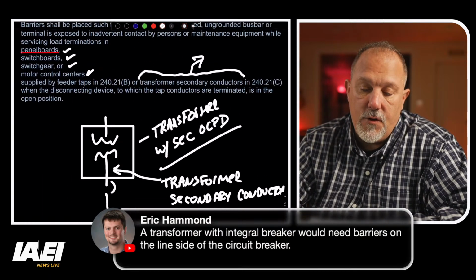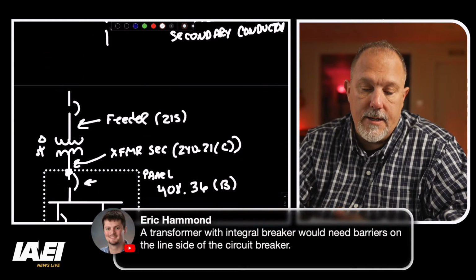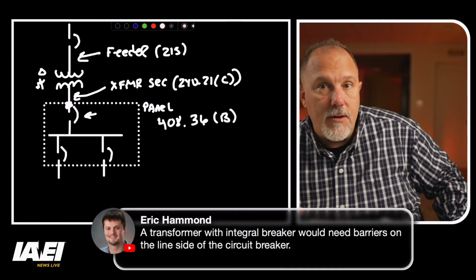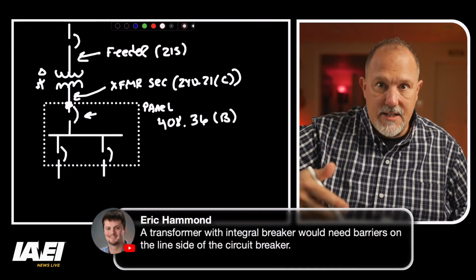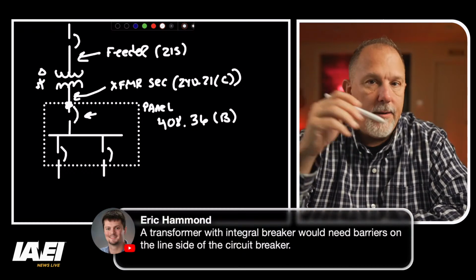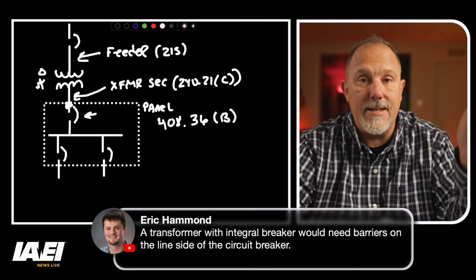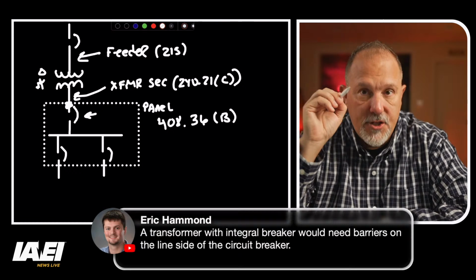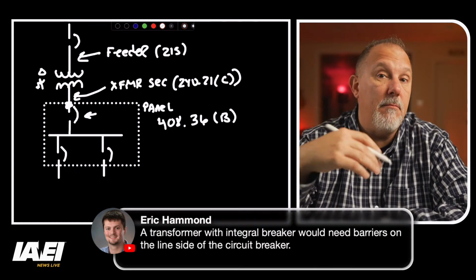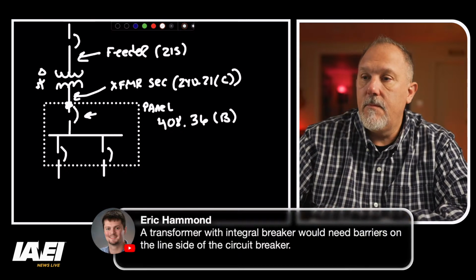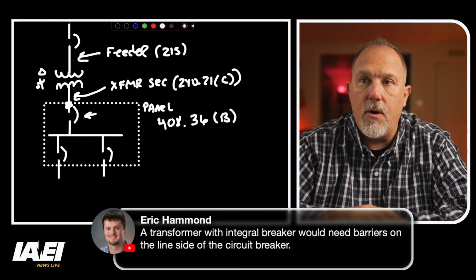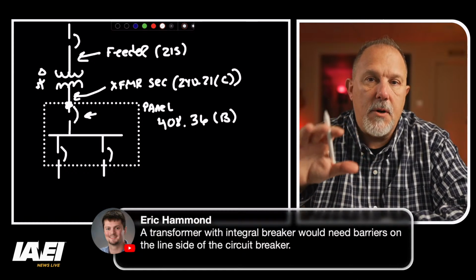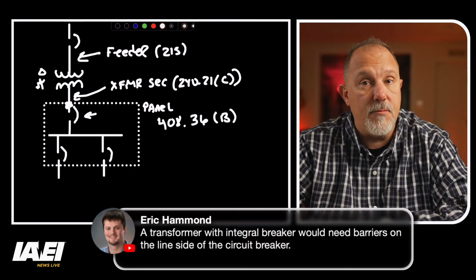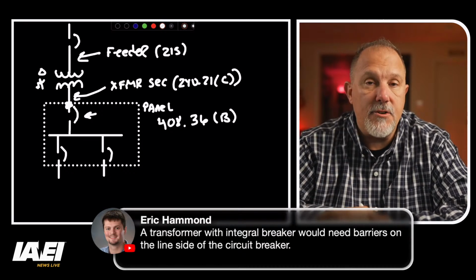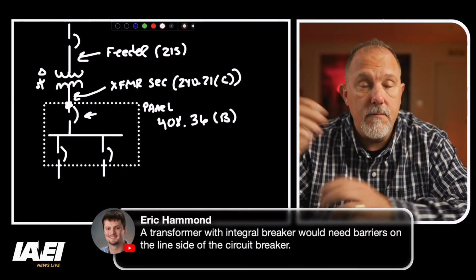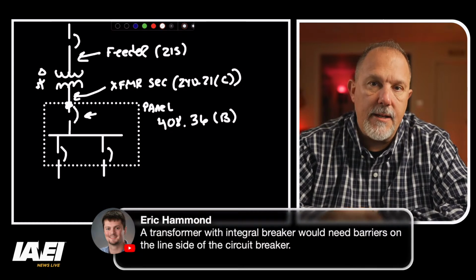So now remember, if you have a transformer that is a listed assembly that comes shipped with a secondary breaker integrated, then you have a listed product. You're not going to open that product and look for X, Y, and Z inside there based on the code because it's a listed assembly. The only time you start picking apart the internals of that enclosure of that listed product is when you see something that has been modified or changed. But Eric, I would say if there needs to be a barrier as part of that listed assembly, that would have to be driven by the product standard. Now, that product standard change could be influenced by this code requirement, but you would not take that listed product apart and apply the code.